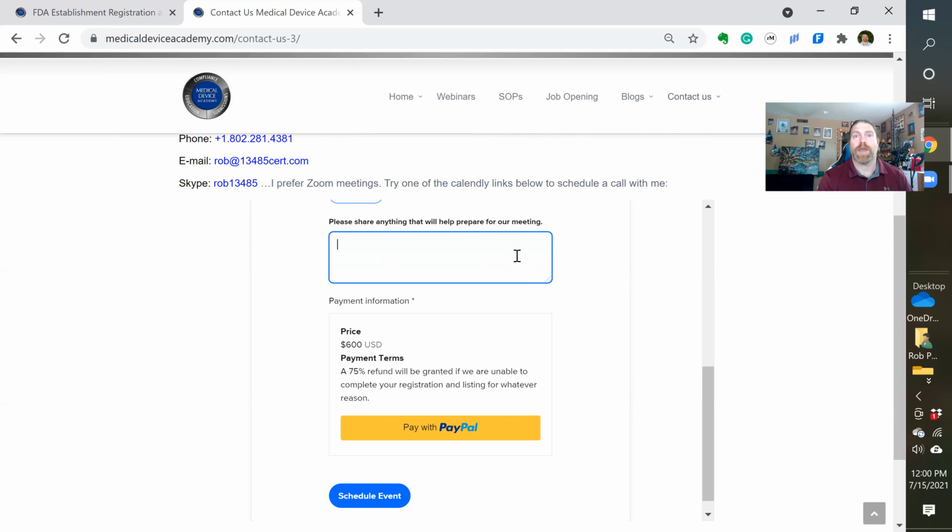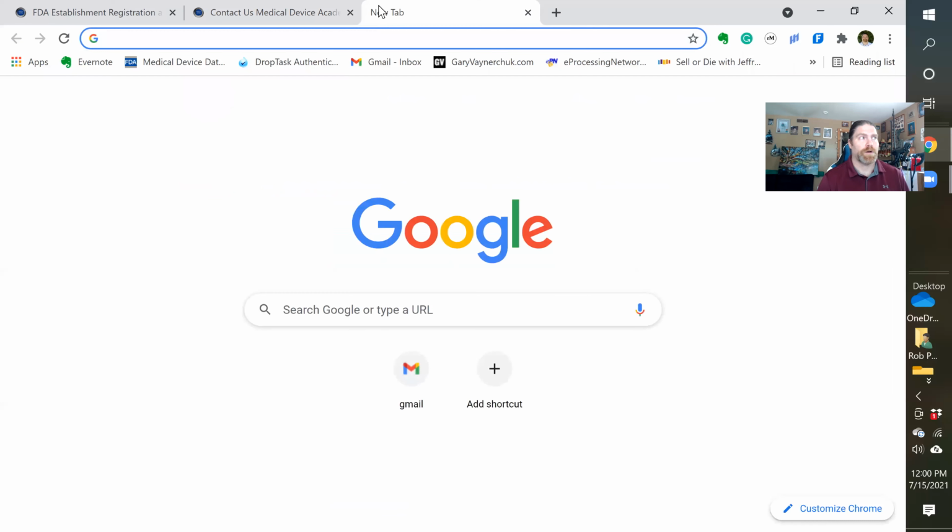So now I'm going to show you how to actually do the registration. As I said, there were two steps. So step one, we have to first go to what they call the DFUF website, D-F-U-F. So the hardest part of all this process is going to be creating passwords and accounts for the FDA. And the hard part about the passwords is uppercase, lowercase, numbers, symbols, can't repeat previous ones, must be a strong password. You get the deal.